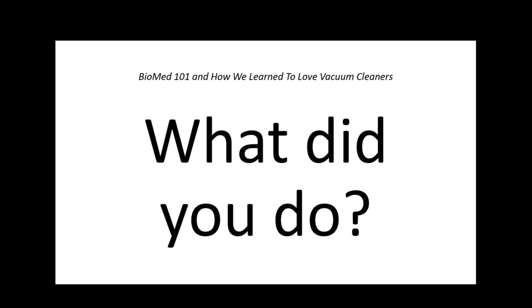I had an MRI service guy for a long time, where I've managed. They have a lot of plastic hardware, plastic screws and nylon screws. Sure, it's the same problem. I used to tell people, if you think it's tight enough, you went too far. You used to have a big lighter and those screwdrivers, and you could melt a new relief in the top of what's left of the screw and get it out.